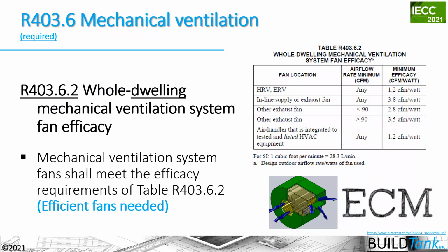We also need to ensure that the fan that we use is efficient enough. So it's important to think about the watt draw that fan has from an energy perspective, because you're going to be running that fan continuously at minimum, and intermittently potentially, and that fan can cost you from an energy perspective. So you want the lowest watt draw fan, and there is actually a requirement based off of this table in the IECC that you need to look at. Now, this is a hard thing to inspect for, so it's really something that needs to be inspected at the plan review side of the equation.